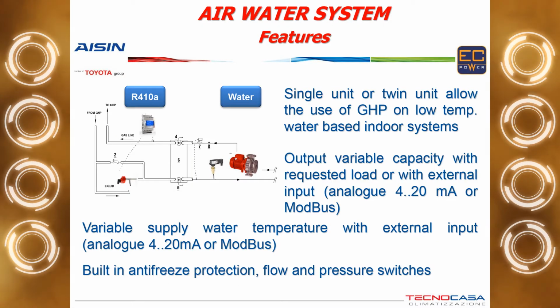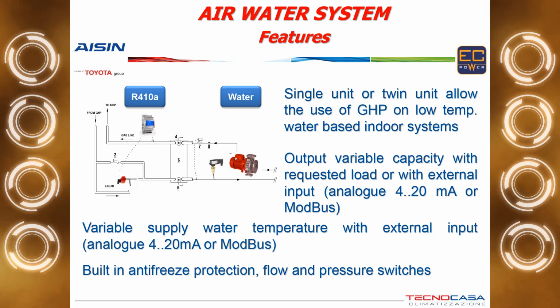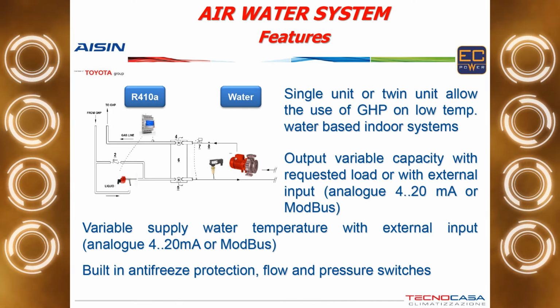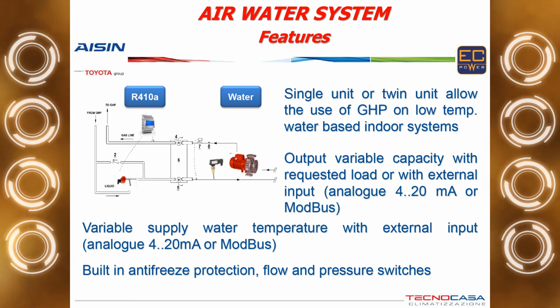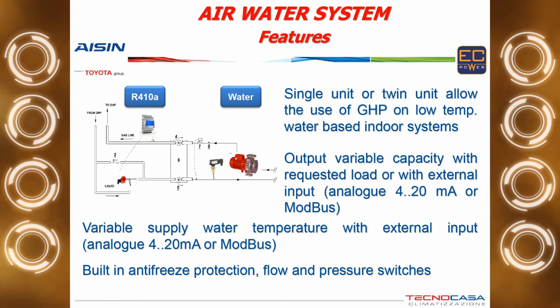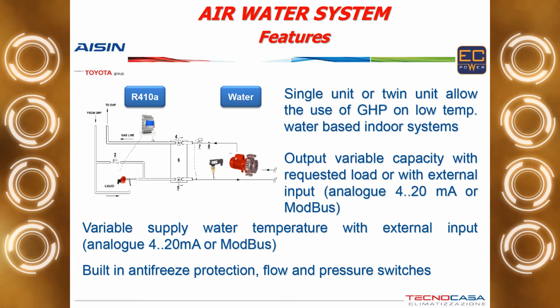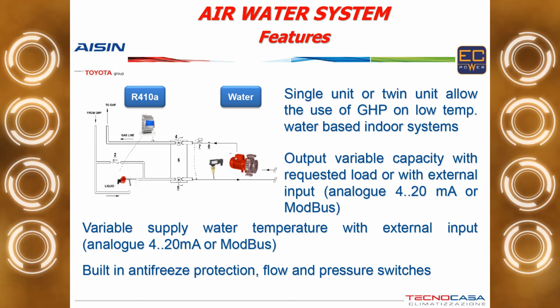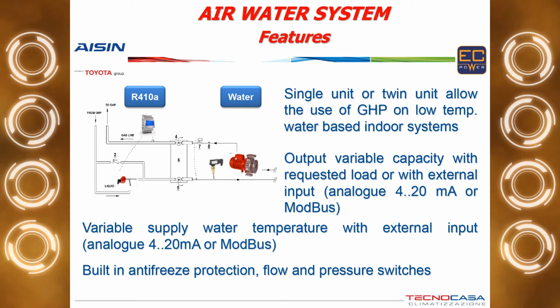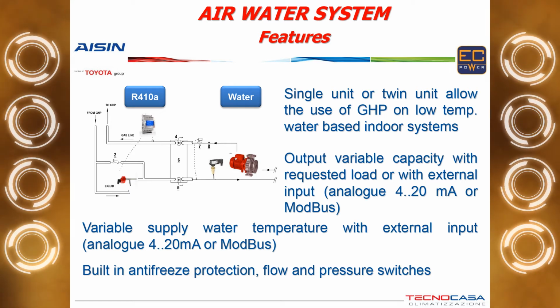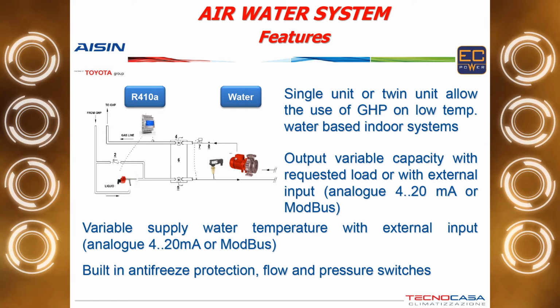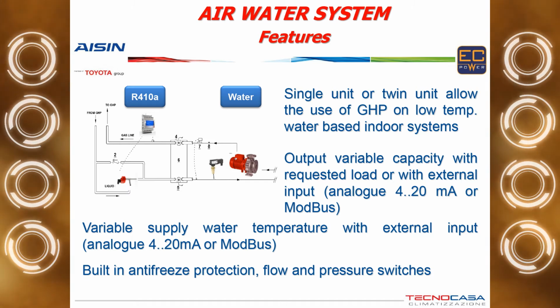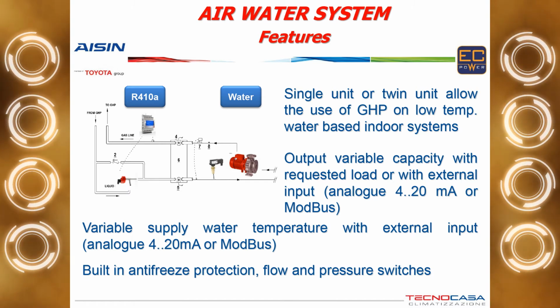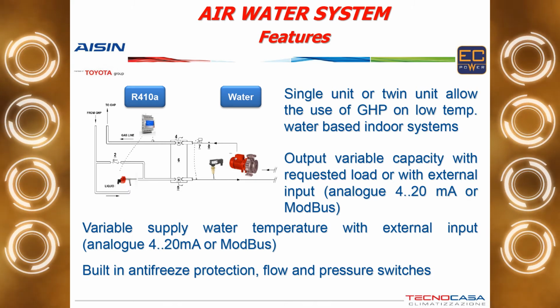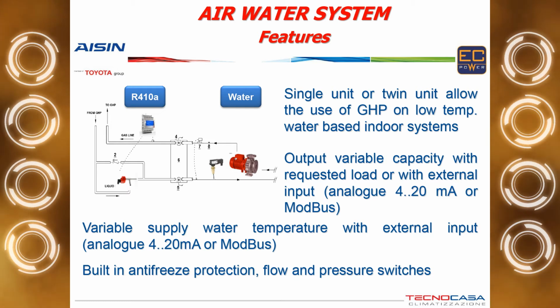The use of R410 and the structure of the gas-driven heat pump do not allow high condensation temperatures. This is why our maximum working temperature in winter is 47 degrees. So it's good for fan coils, it's good for underfloor heating, it's good for air handling units.